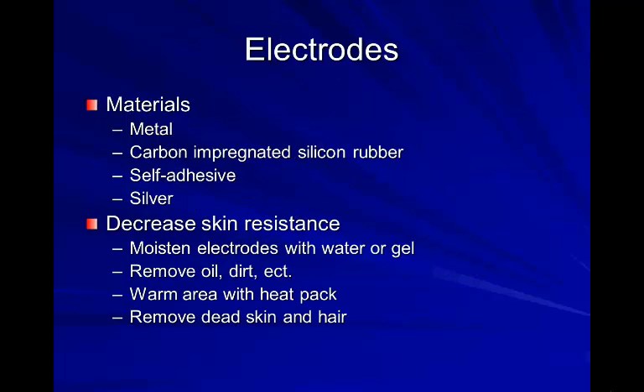Electrodes can be made from various materials. Back in the old days they had sheet metal electrodes that required a wet sponge. They also had carbon-impregnated silicone rubber, a black rubber pad that comes in various sizes — again requiring ultrasound gel or a wet sponge. Then you have the silver self-adhesive sticky pads, which are commonly used today.